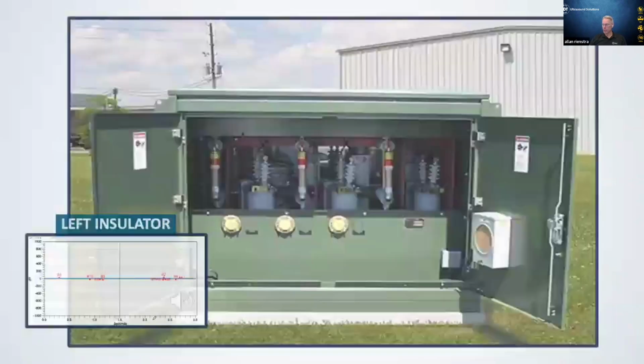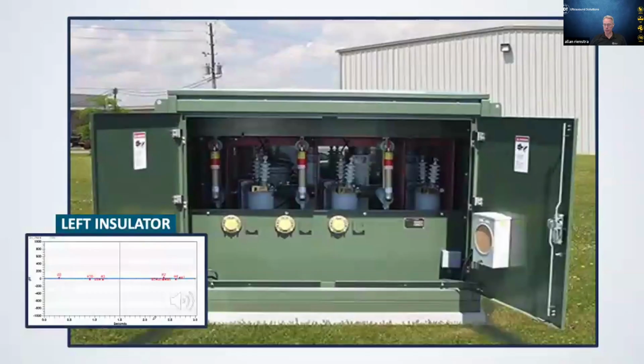Here's a commercial insulator, a commercial 3-phase transformer, pretty standard stuff. You drive around any industrial park, you're going to see lots of these hanging around. We've opened the doors up on them. Now we had detected, using a contact sensor with a magnet on it, much the same way a doctor might put a stethoscope on your chest, we put a contact sensor on the outer housing, and through the steel, we were able to hear that there was some corona activity present.